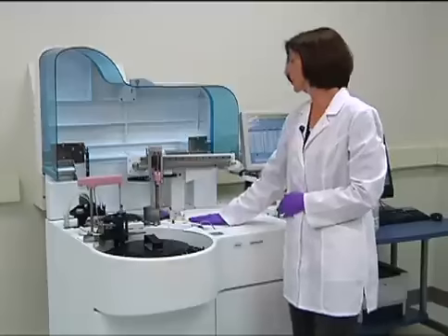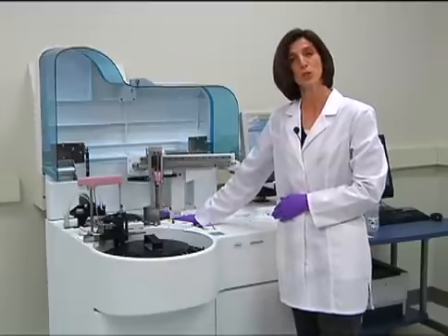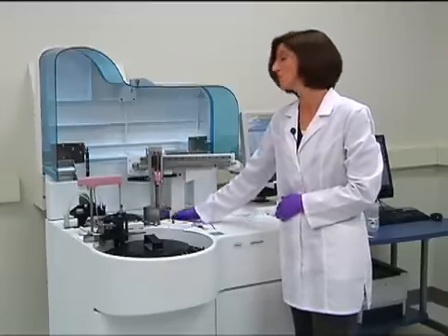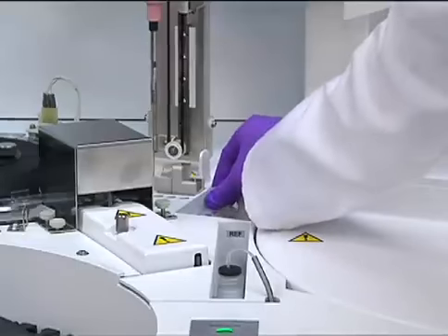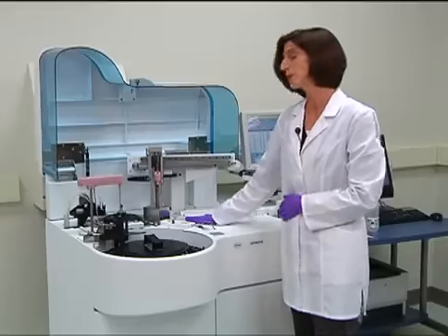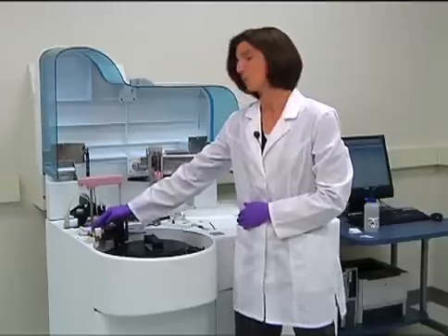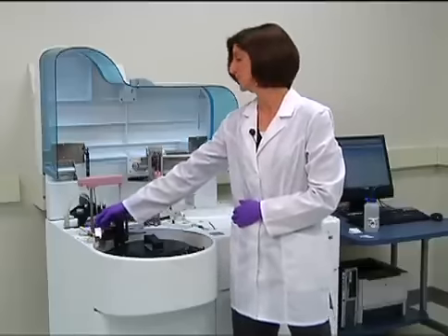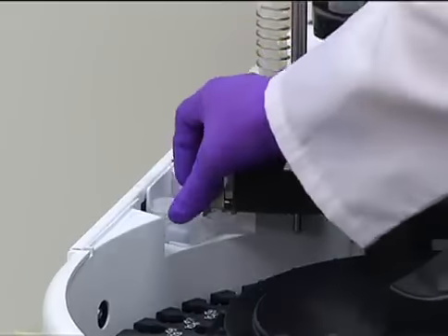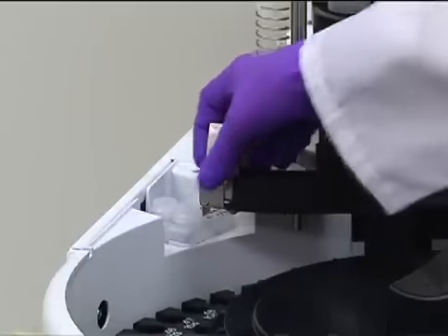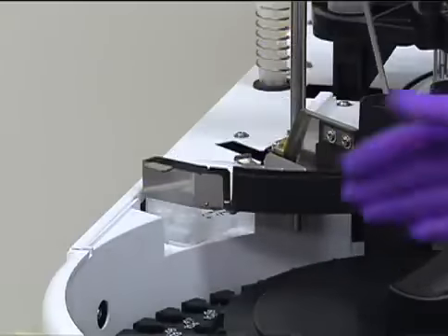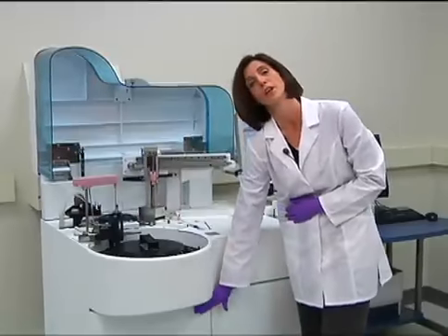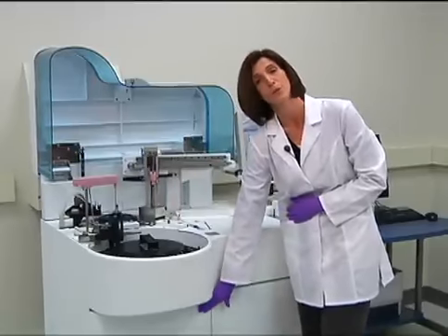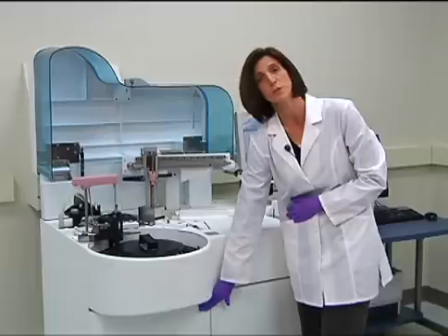The ISE reagents are located next to the reagent compartment and are liquid and ready to use. So we would simply remove the old bottle and load the new one in. Sample probe detergents are located next to the sample disc, and again, liquid and ready to use, so we would simply remove the old bottle and load the new one. Also, we have detergents located at the bottom of the instrument that are liquid and ready to use. So we would just replace the old bottle with the new bottle.